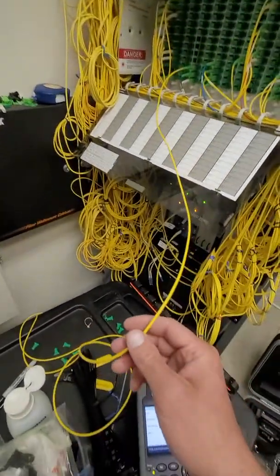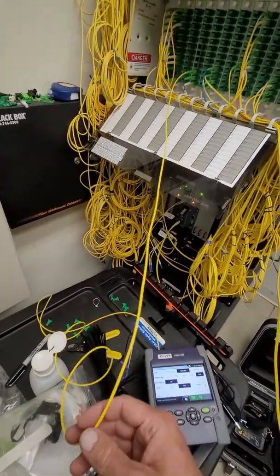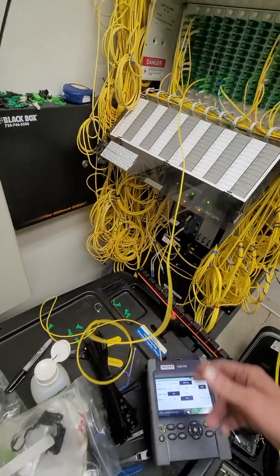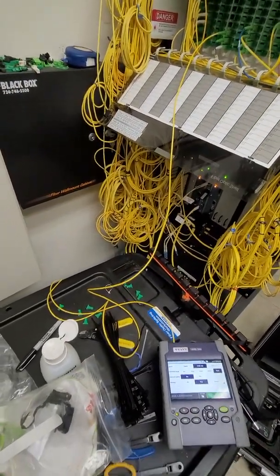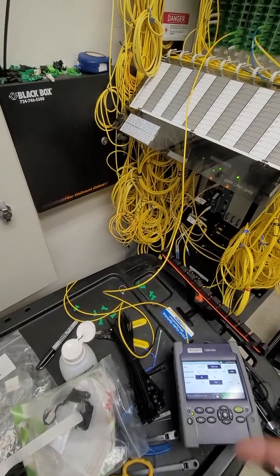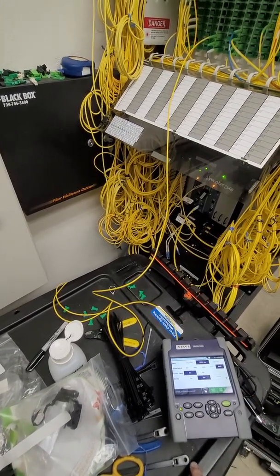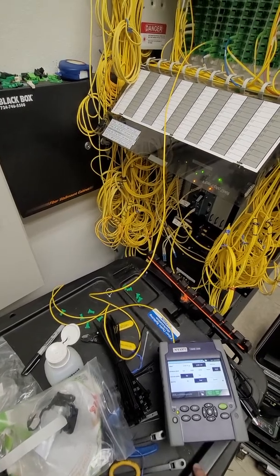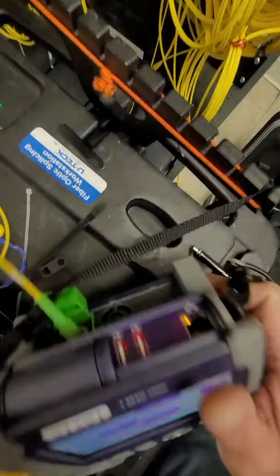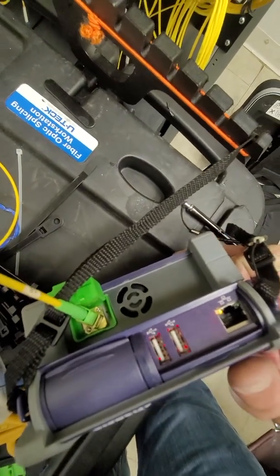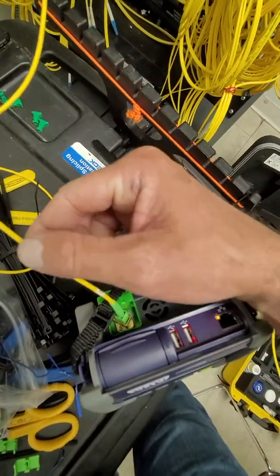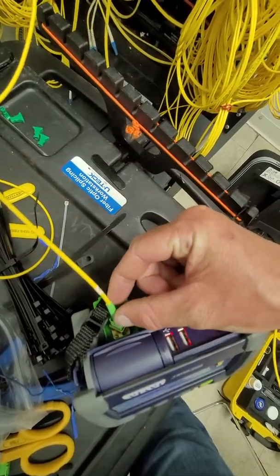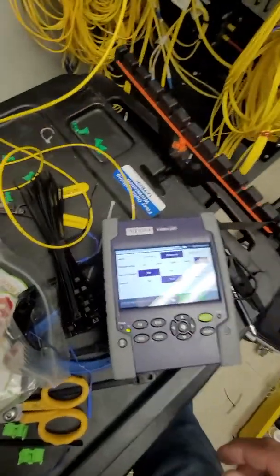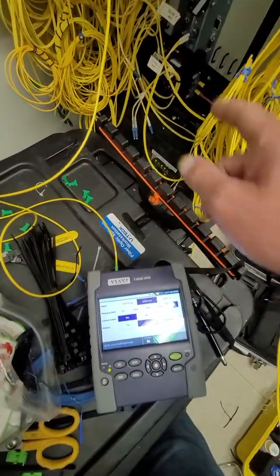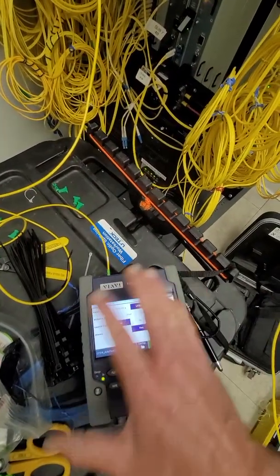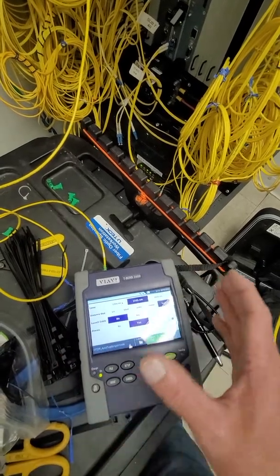Now, I do want to disclose that normally when you're shooting a fiber optic circuit, you want to use what's called a launch reel. And the reason why you want to use a launch reel is it has a distance of about 1,000 foot, sometimes 320 foot. It just depends on what kind you buy. The light coming out of this device, which is the OTDR, is sometimes so strong that it will reflect off the inside of this cable and come back and actually distort the data within the unit. So you need that launch reel for the unit to be able to tell itself, hey, I'm going to spot the first 1,000 foot.